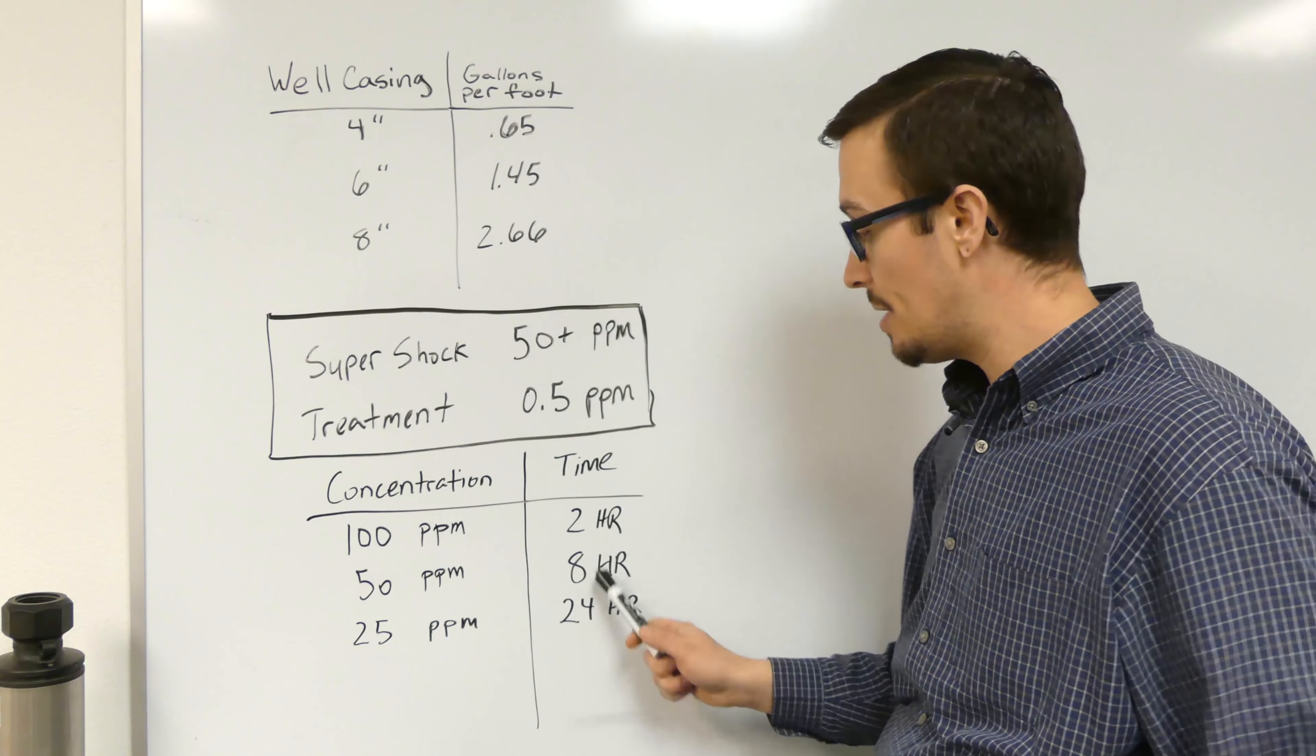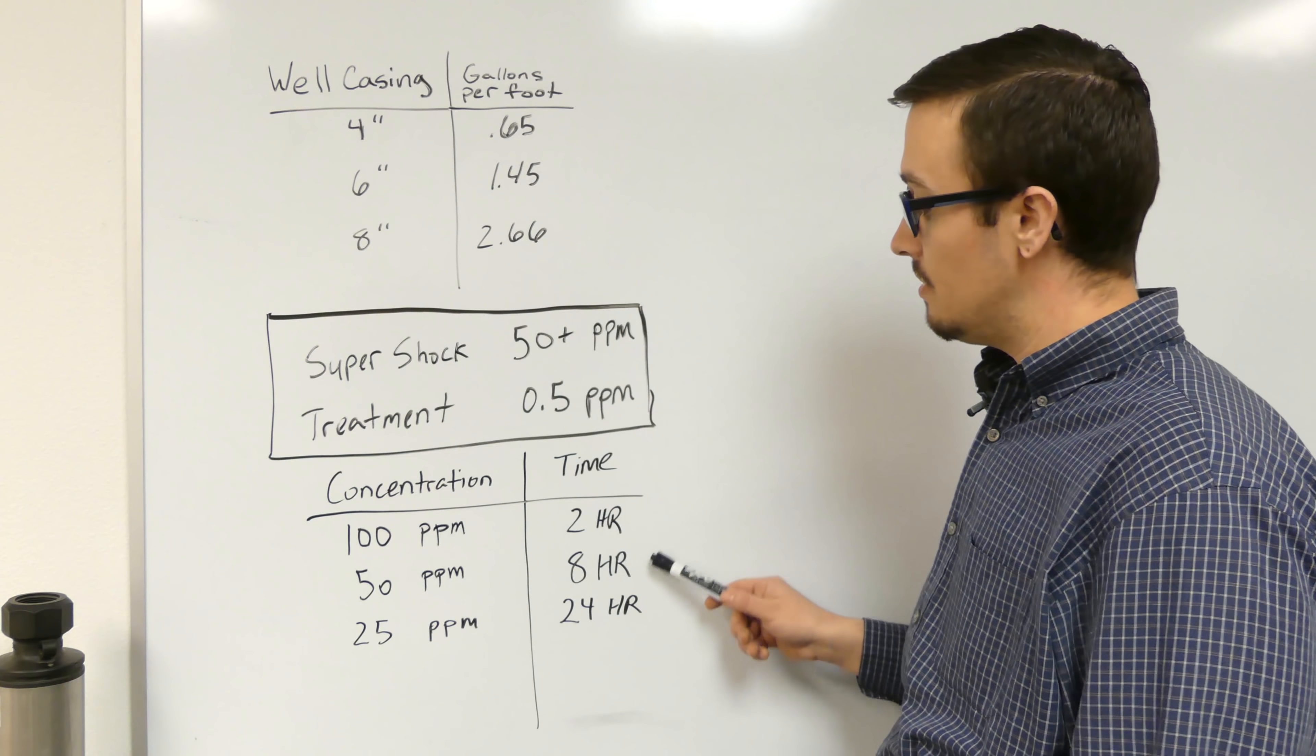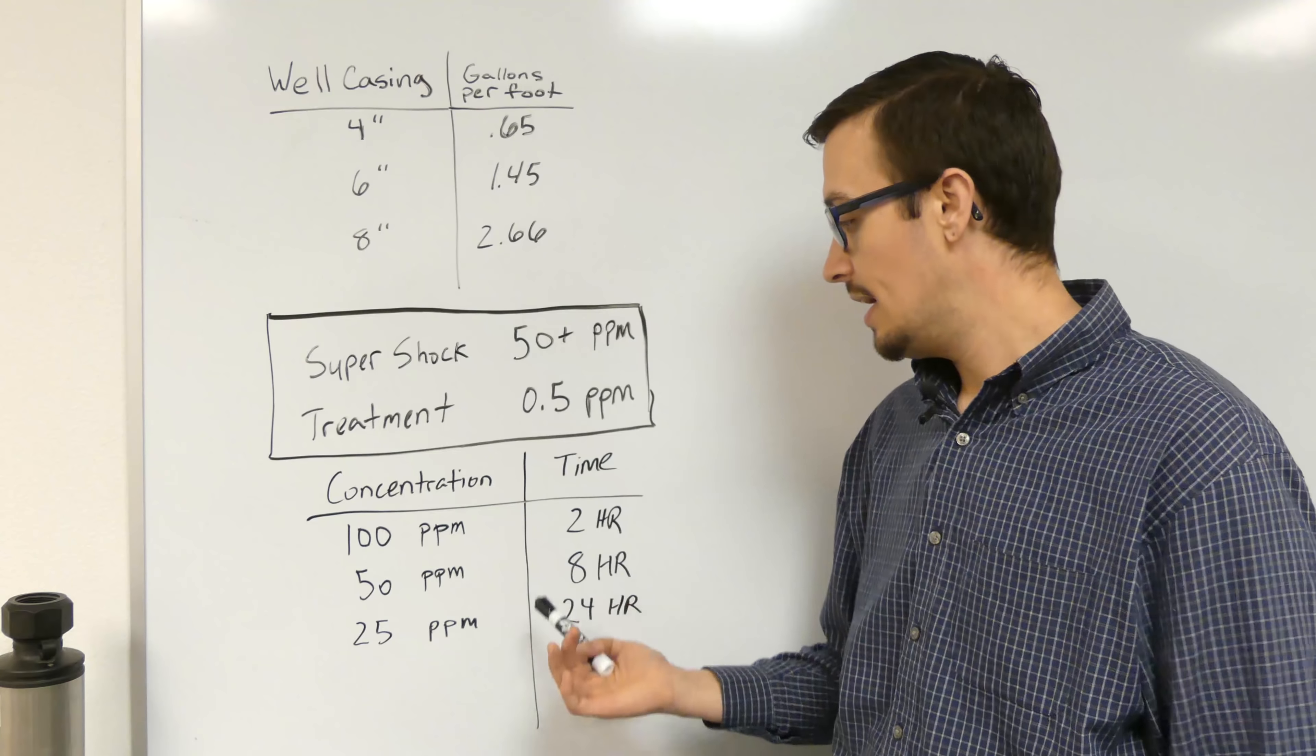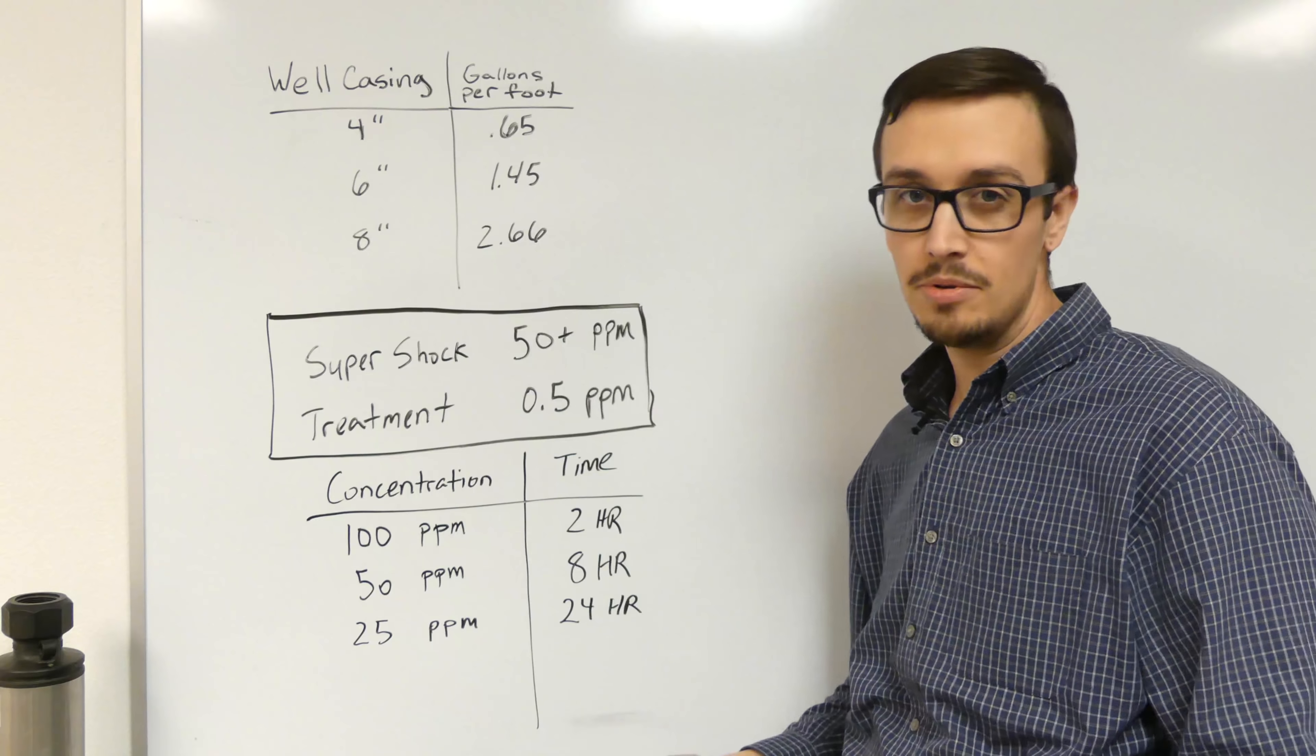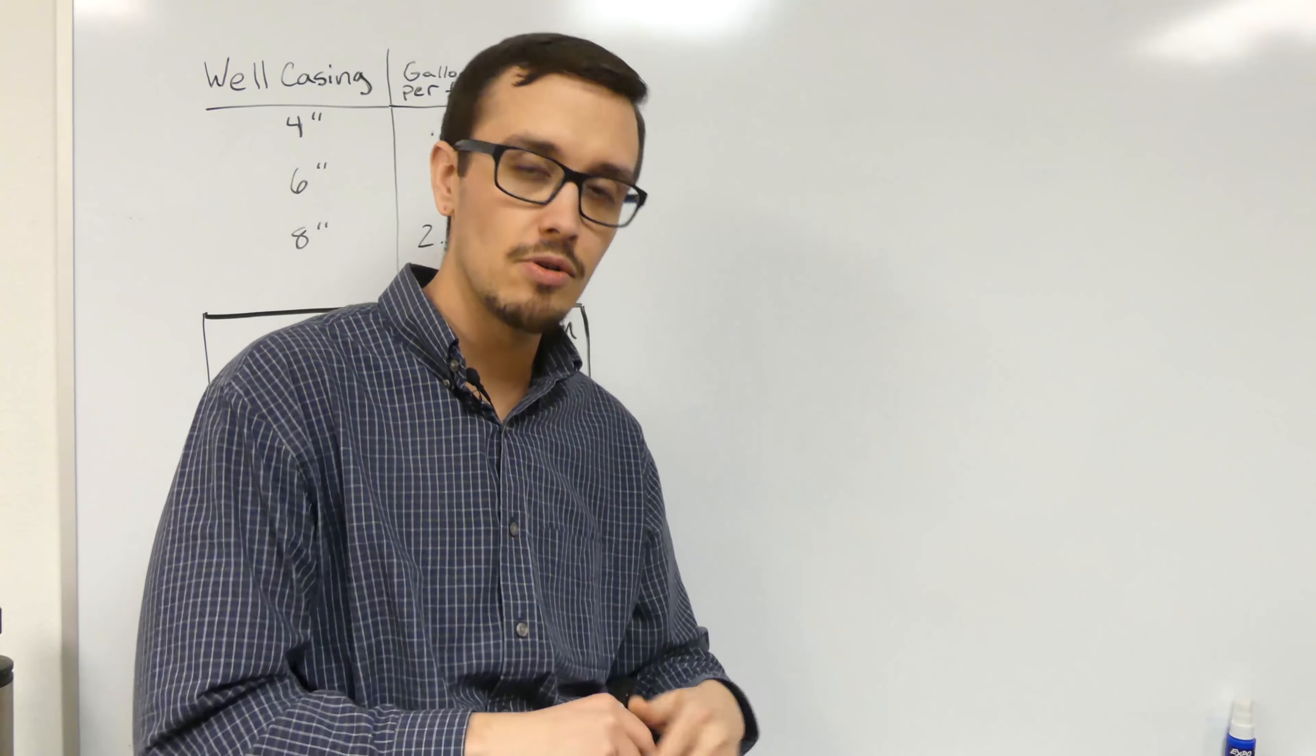The higher the concentration of chlorine, 100 parts per million versus 50 parts per million for example, you're going to have a dramatically shorter retention time. If we actually half the amount of chlorine, the length of time increases fourfold. We go from two to eight hours. You can decide based on your schedule how much time you have, and you might be able to use a little bit less chlorine, get longer retention times, and so forth.